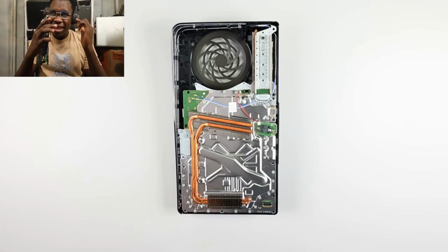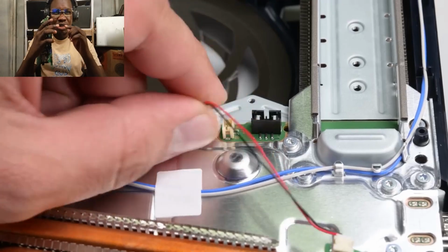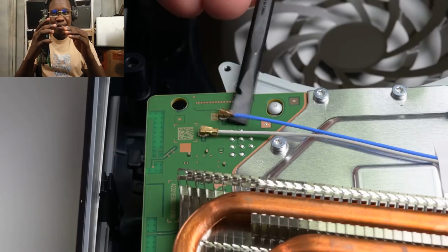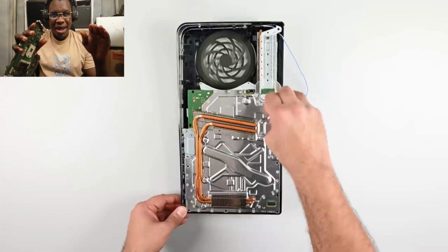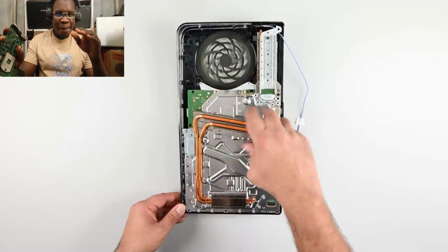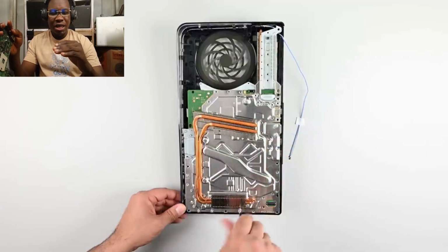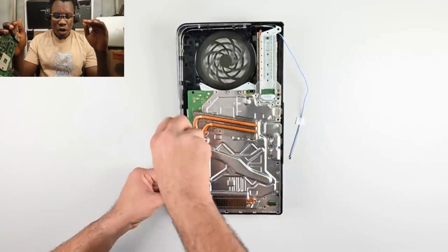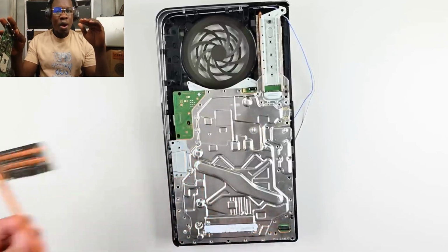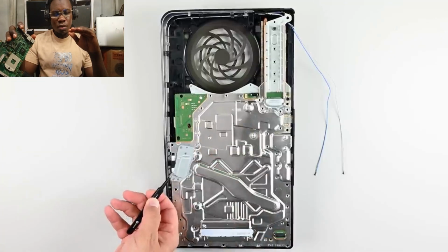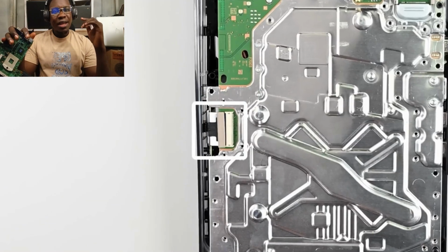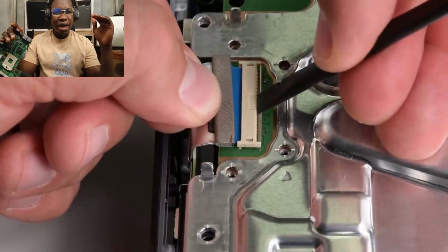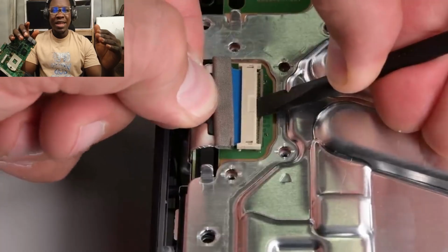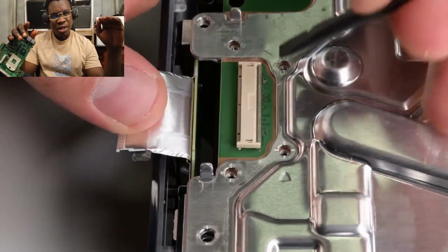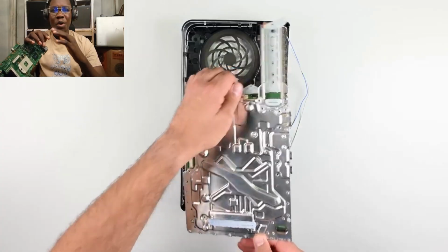Once the airflow drops by even 20%, the internal heat package will saturate the heatsink, forcing the liquid metal to its absolute thermal limit. What that means is liquid metal, even though it's a good cooling system, it has a limit. So if the fan clogs and the airflow percentage drops down, it's going to rise to its maximum limit that it's supposed to go. And if it hits the maximum limit, the next thing we are going to see is auto shutdown.